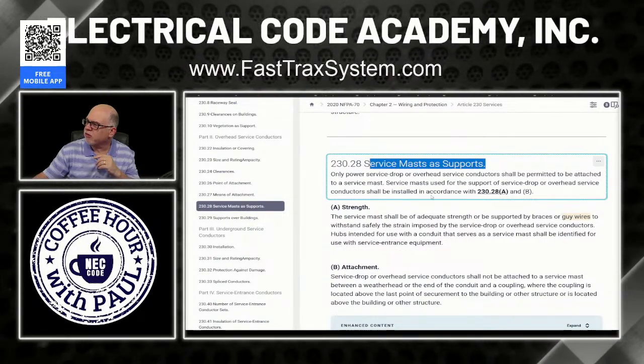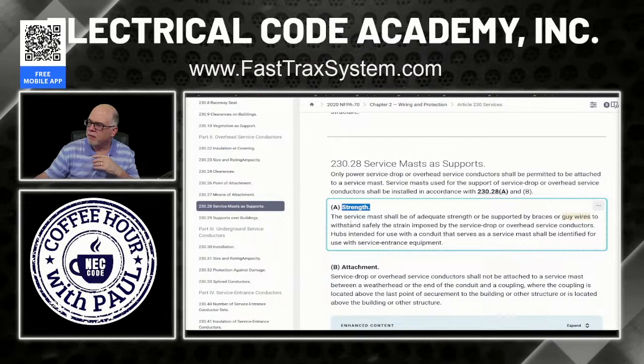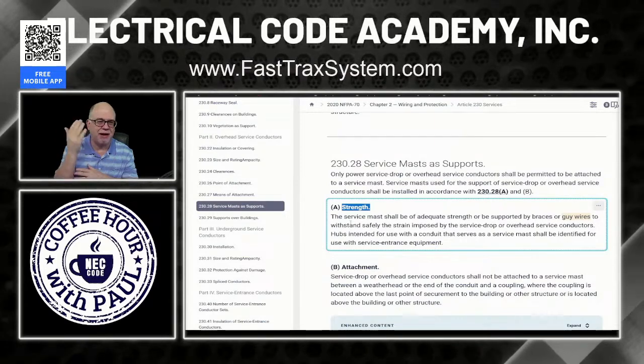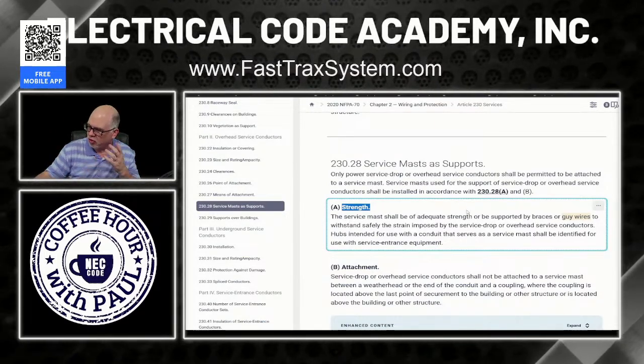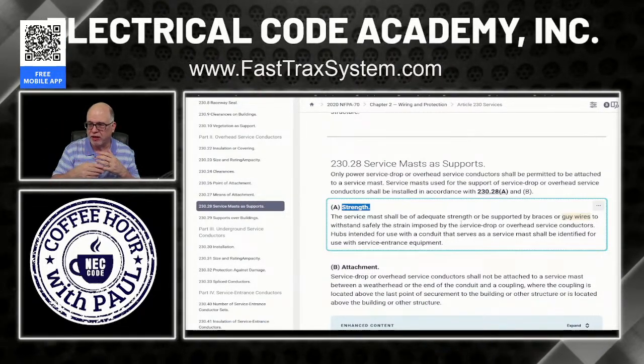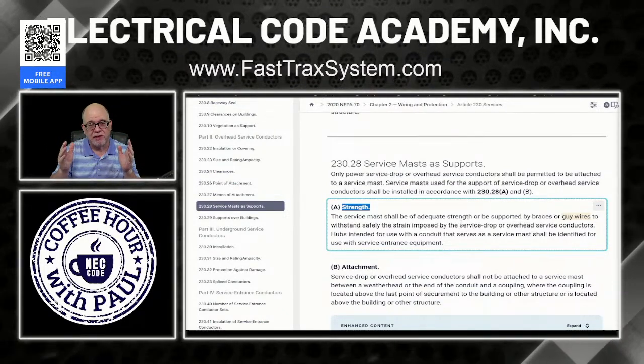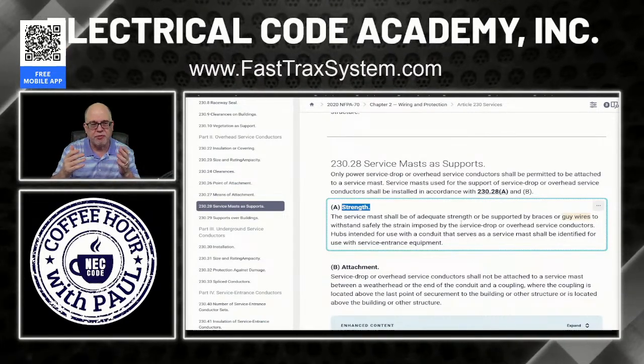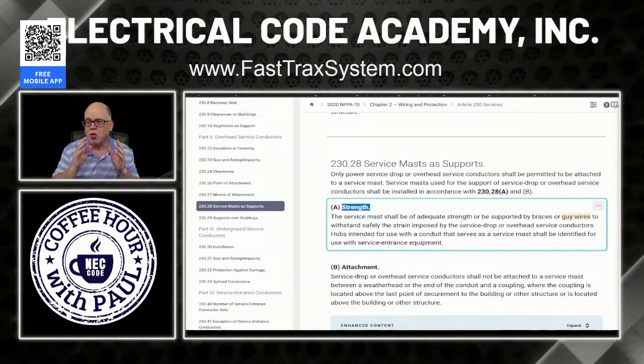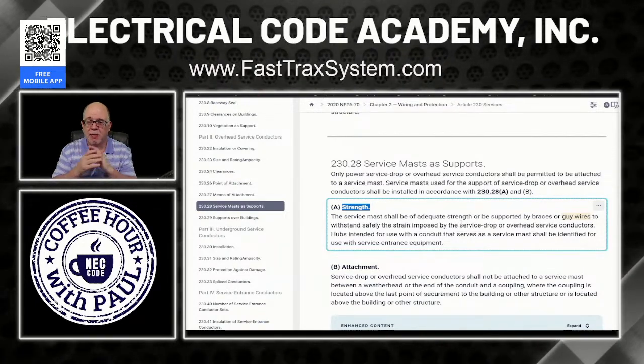All this information is basically what we regurgitated, but let's talk about this strength. Obviously, you're not going to extend PVC up, right? Heat of the day, bends, that tension from the service drop, that's not going to happen. This is where the mast is supporting the drop, if it's a utility service drop, or if you're the electrician and you ran the overhead service conductors. If you don't know the difference between overhead service conductors, service drops, service laterals, underground service conductors, and service entrance conductors, go to Article 100. It's pretty self-explanatory, but we're going to have a video coming up on that.